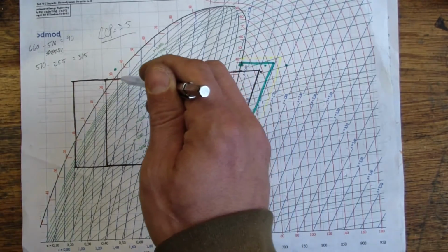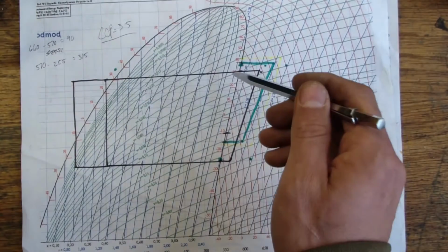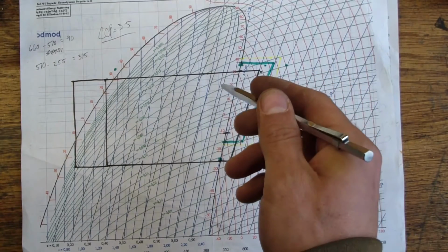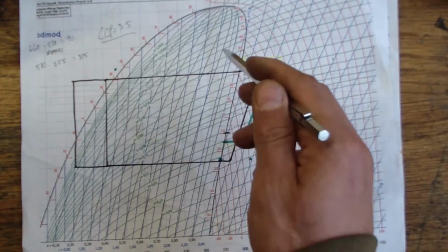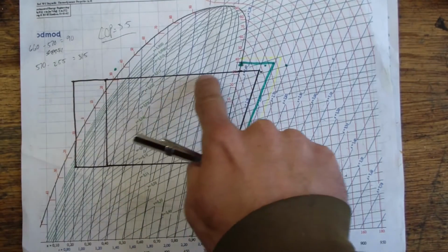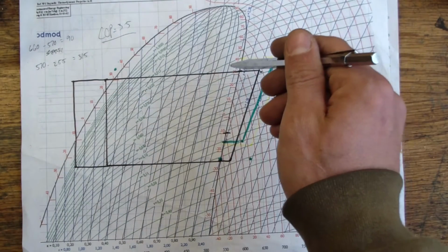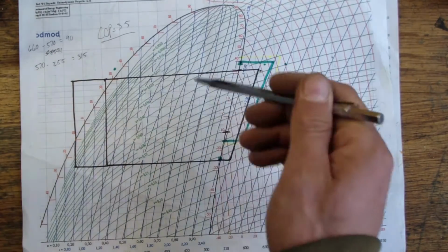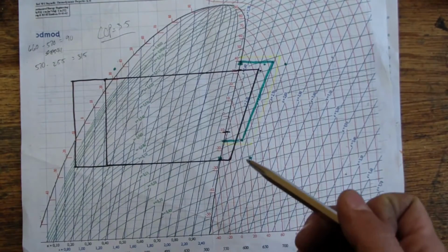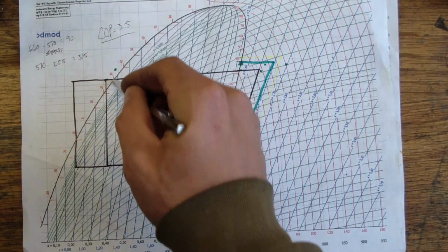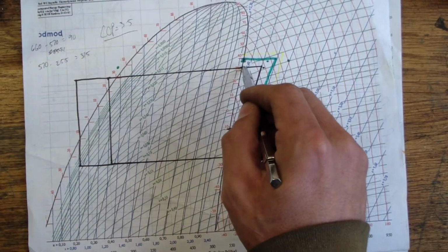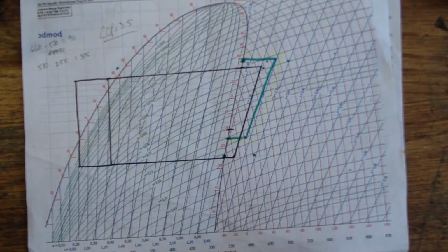So as we travel across at a constant pressure and a constant temperature that we're condensing, the quality of the refrigerant changes. It's not really too important to discuss that, but if you take this line and you divide it by 100 parts, then right here you have 100% quality, and here you have 0% quality. I misspoke there. So the quality is the actual amount of vapor. So purely liquid, saturated, is 0% quality. Purely vapor, saturated, is 100% quality. Again, not too important there, but just to get a general idea of where it exists there on that isobaric line, that is line of constant pressure. Okay.